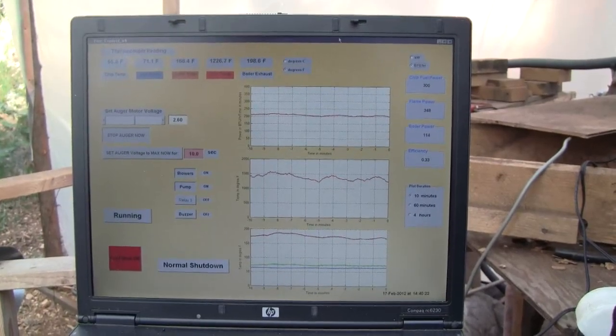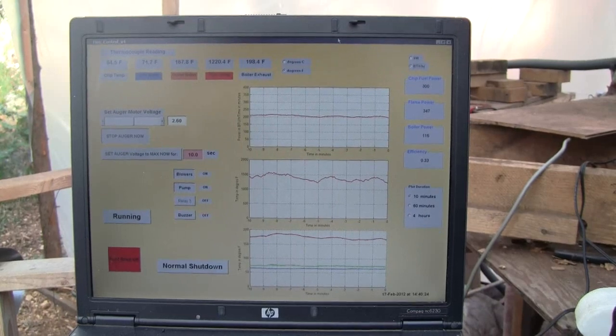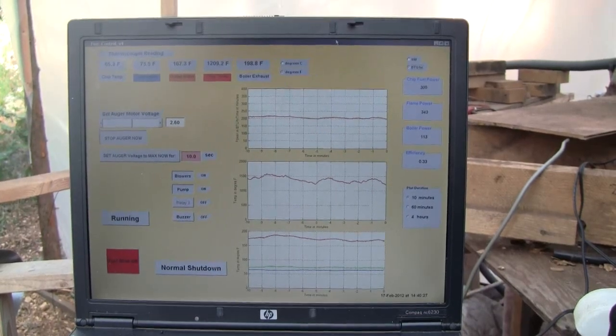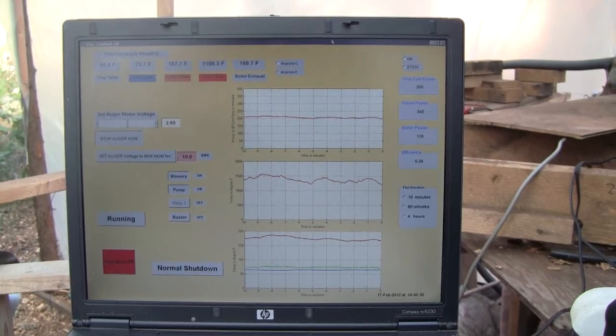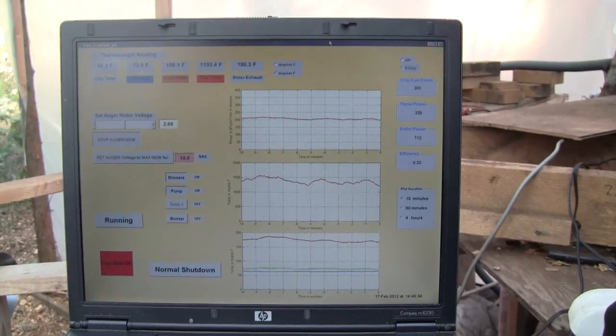Inlet water, that thermocouple is bad, the inlet water is really warmer than that so that needs to get fixed. Outlet water is reading about correct and flue temp is reading correct as far as we know as is boiler exhaust.